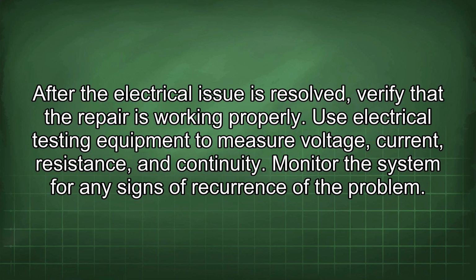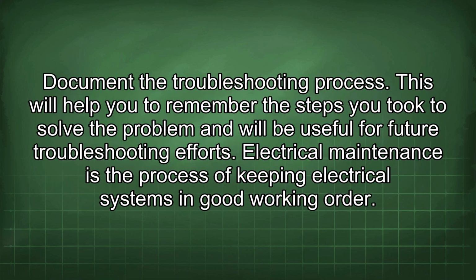After the electrical issue is resolved, verify that the repair is working properly. Use electrical testing equipment to measure voltage, current, resistance, and continuity. Monitor the system for any signs of recurrence of the problem. Document the troubleshooting process. This will help you to remember the steps you took to solve the problem and will be useful for future troubleshooting efforts.